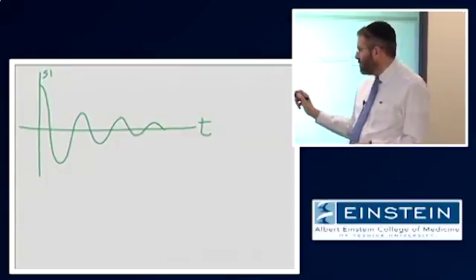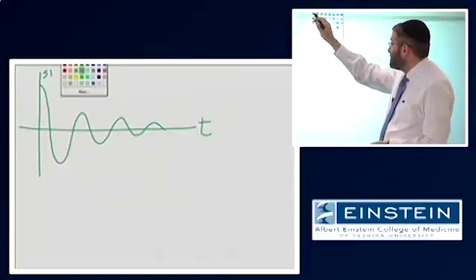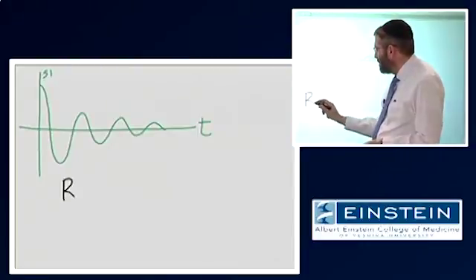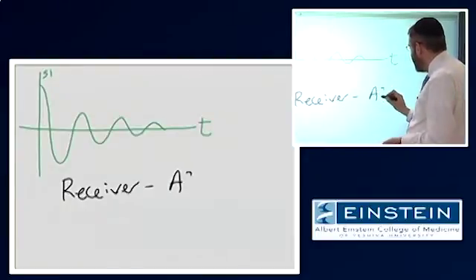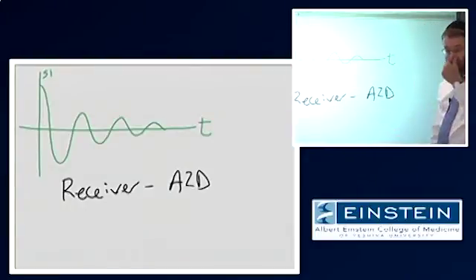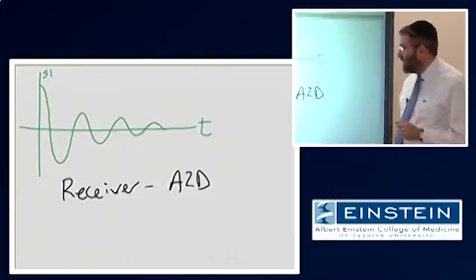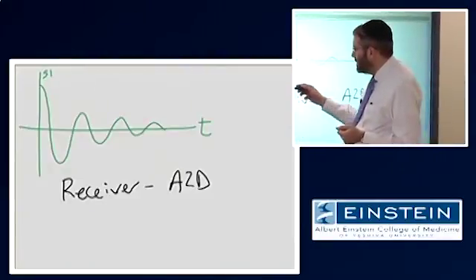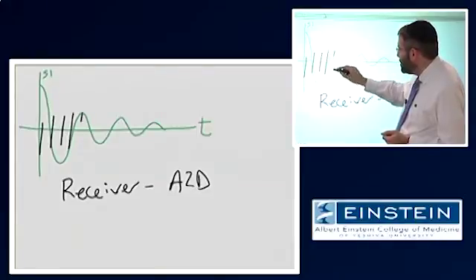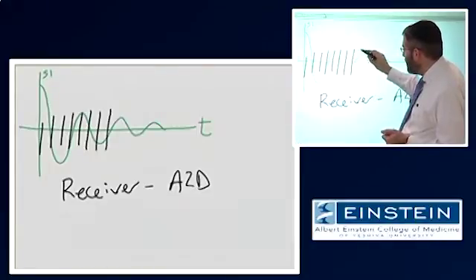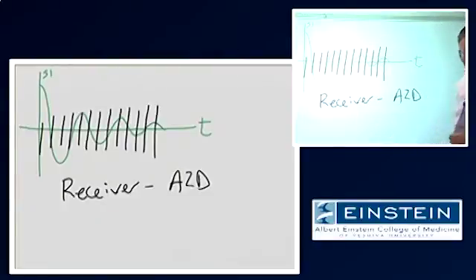So there is another piece of the MR system, which is called the receiver, or also known as the A to D, or analog to digital converter. All that is, is complicated, but for our purposes, that is essentially just a piece of hardware which takes this signal and essentially chops it up into a series of discrete measurements.